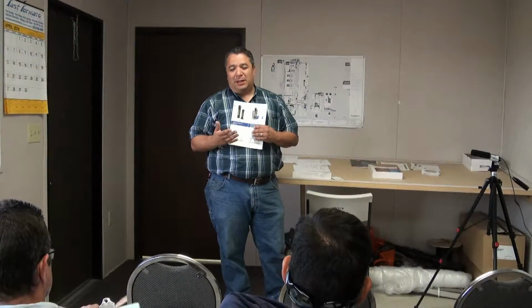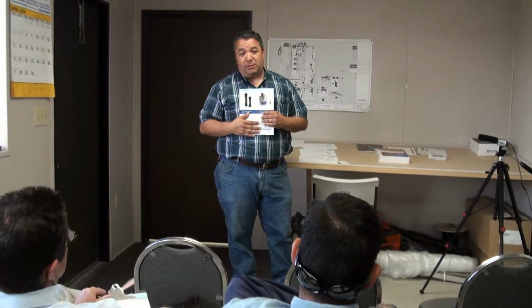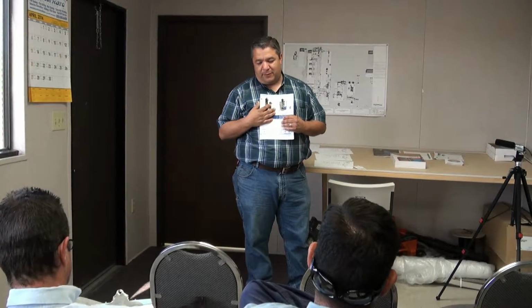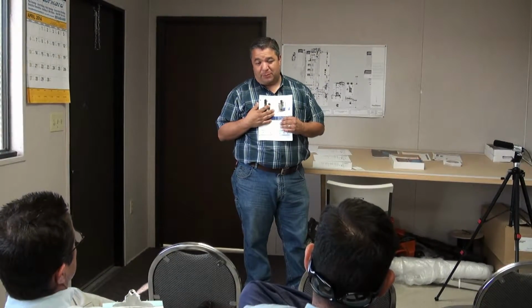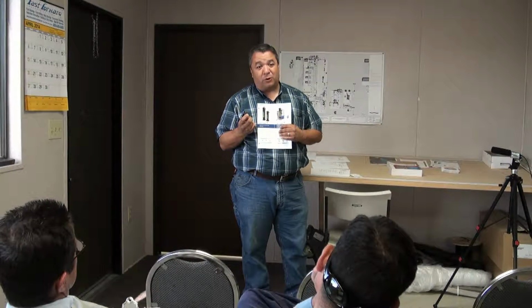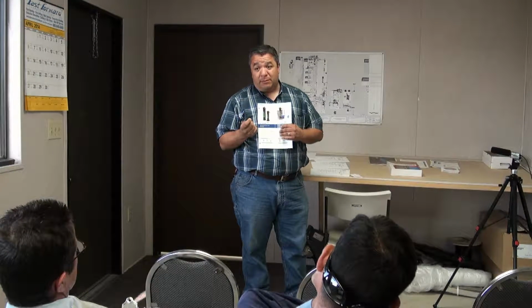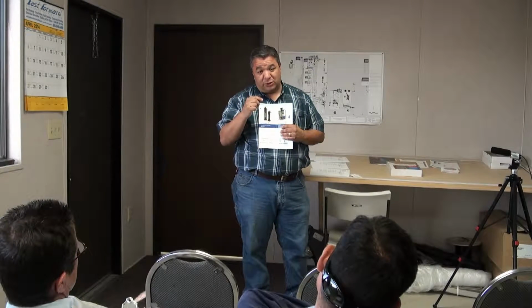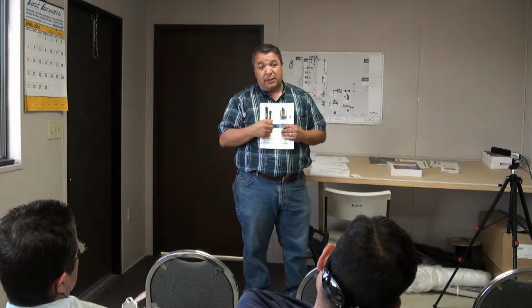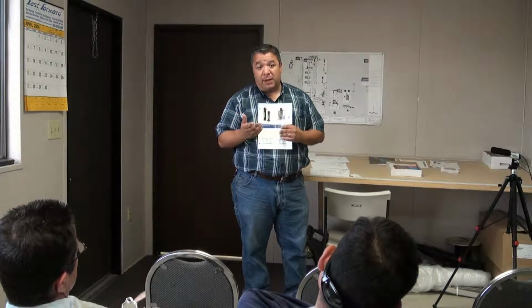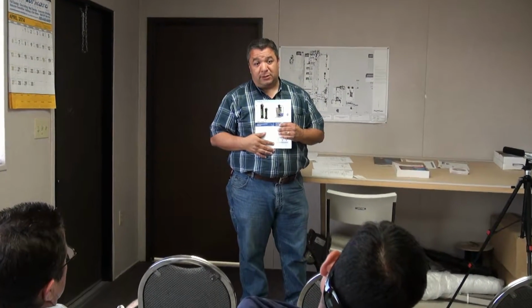Here's the problem, and Lakos knows about it, but it's a cost issue for them getting out to people. The switch, in my sense, after a couple years, that switch is not going to work well as it should. You need to clean them - get in there, take it out, blow the pipes out, make sure there's no debris in the springs. You've got to take them out, it's part of the maintenance of that little DP sensor.